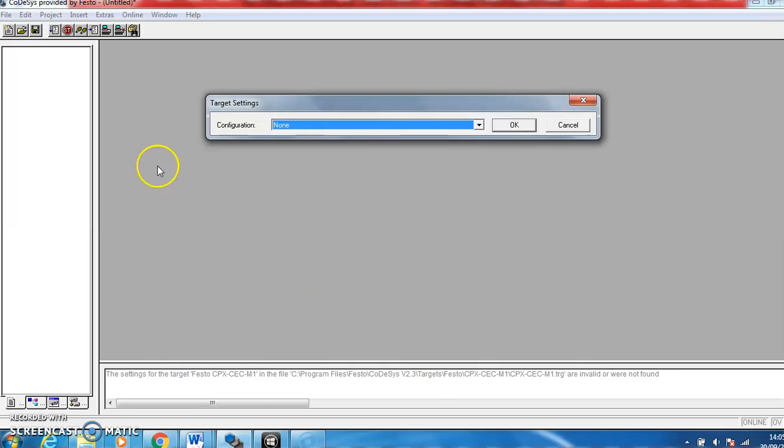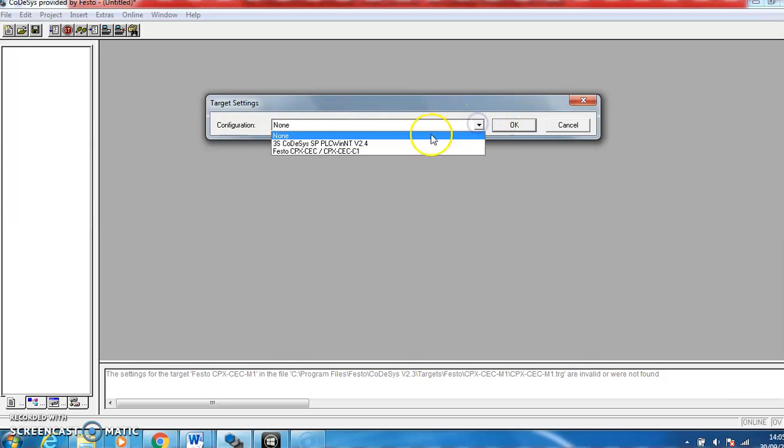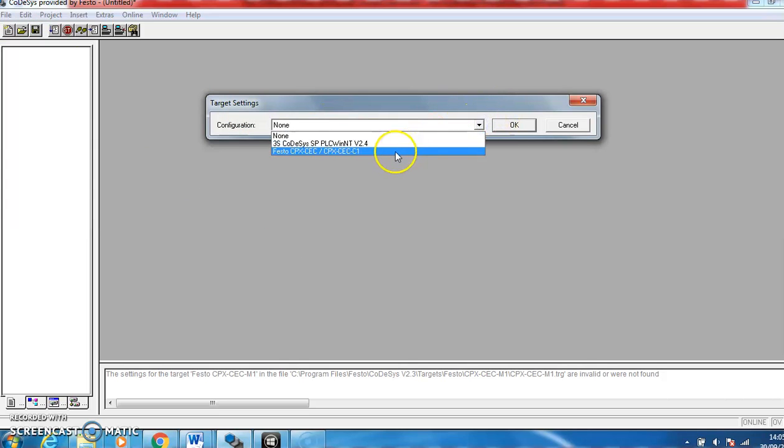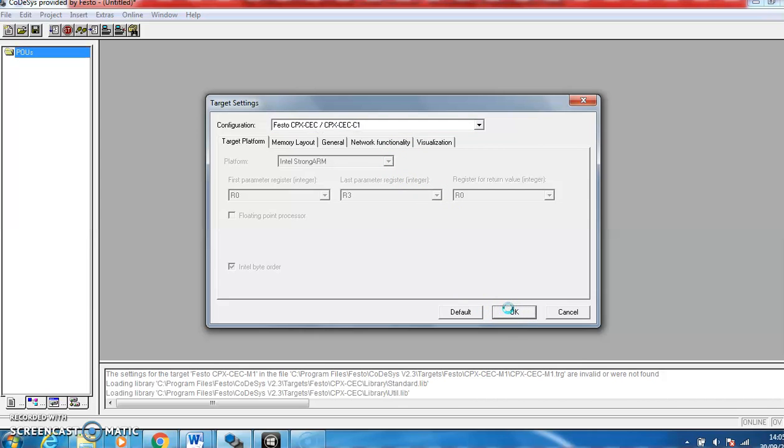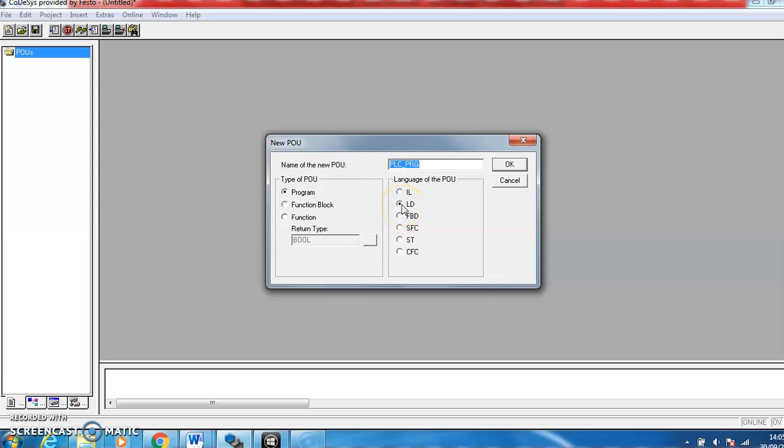So to program this we're going to start with a new program. When you go File and press New, you'll get this target settings up here. Make sure you choose Festo CPX-CEC / CPX-CEC-C1 as that's the PLC we're programming for. Give that an okay, leave PLC_PRG there, make sure Program is ticked and LD Ladder Diagram.